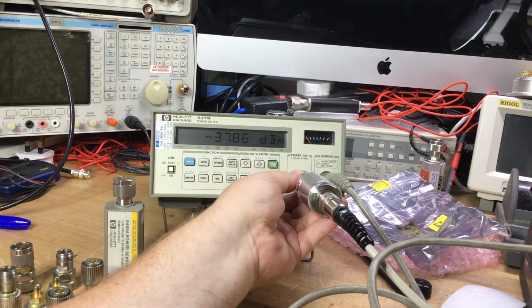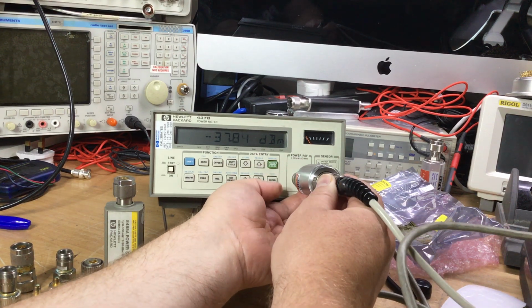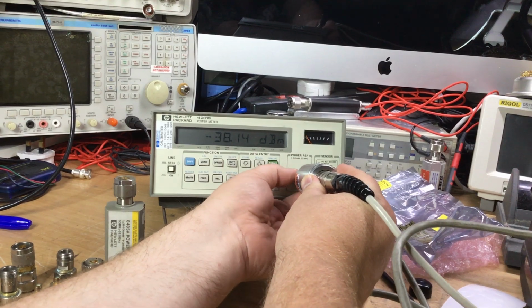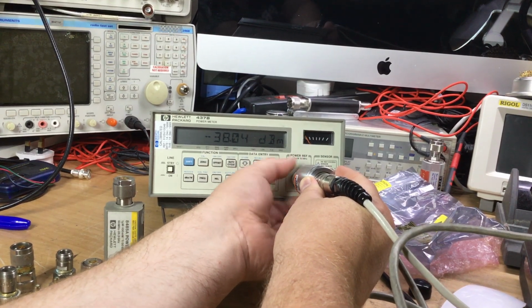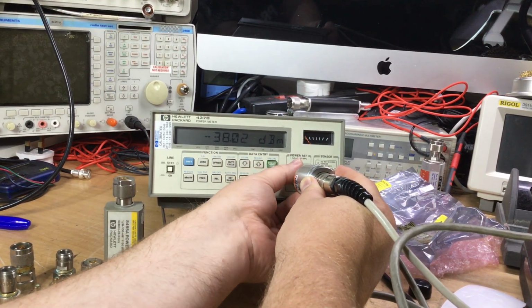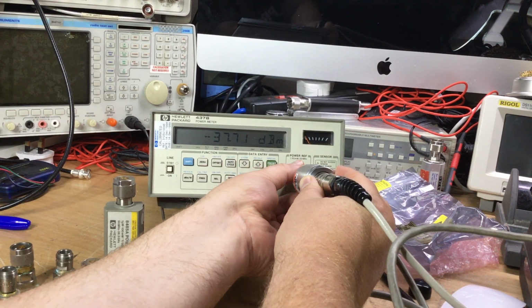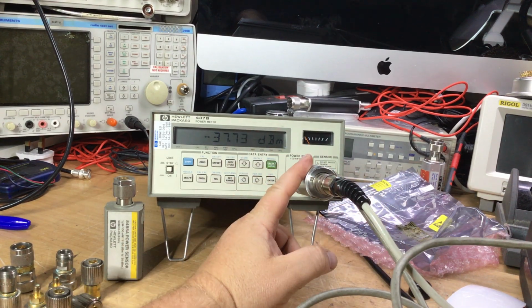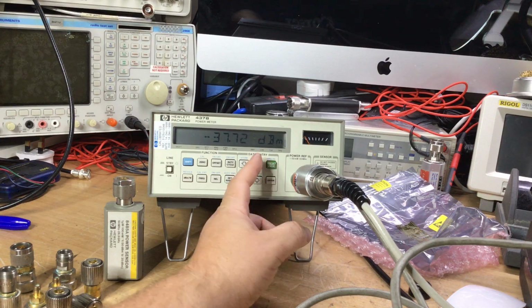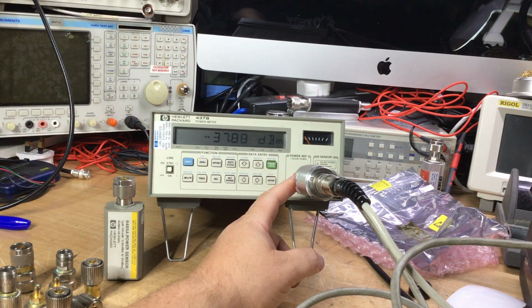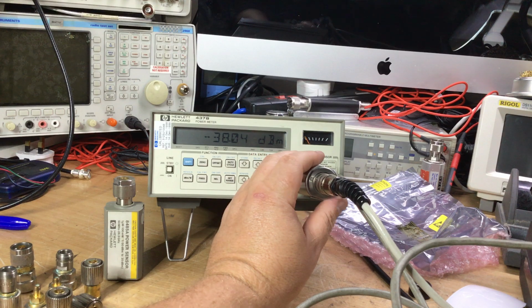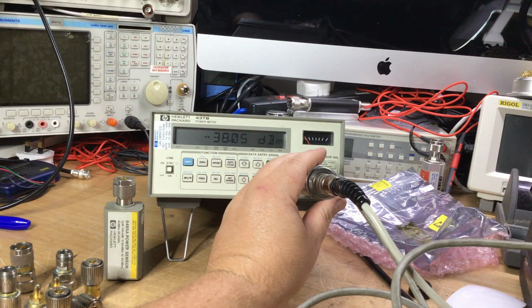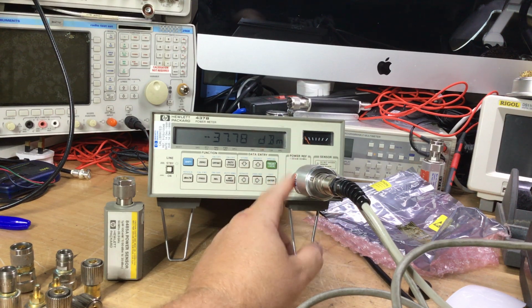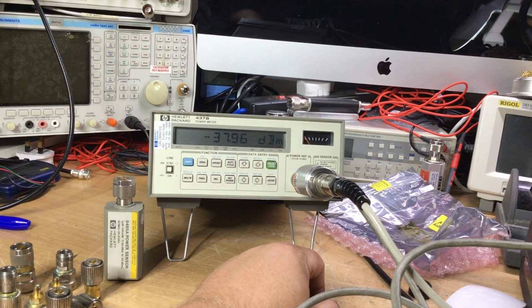So that's what we're going to do now, and what we do is we support the body of the sensor, and we turn the collar to the Type N. Never rotate the sensor because it causes damage. They're gold plated contacts in the Type N, which must be kept damage free and clean, so that's why you never turn the body, and it causes damage to them.